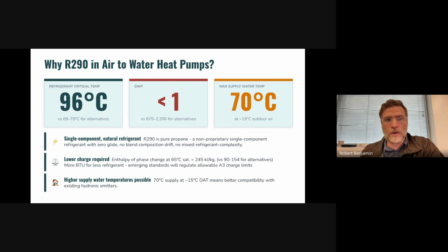But when we look at R290, it has a couple of attributes that go above and beyond just being an ultra-low GWP refrigerant. It's a single component refrigerant, and looking at the complexities around mixed refrigerant blends, any leakage, and how systems react to it, having one single component really helps. It also helps that it's not a proprietary blend that may be hard to get at some point.